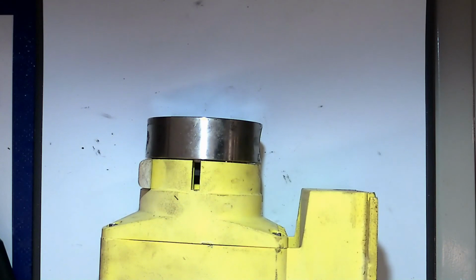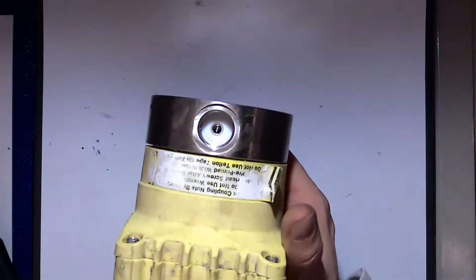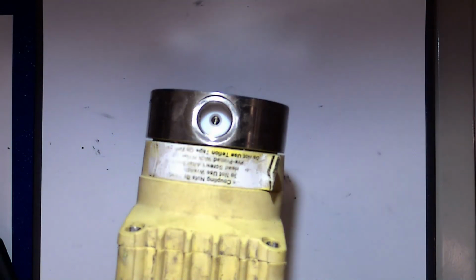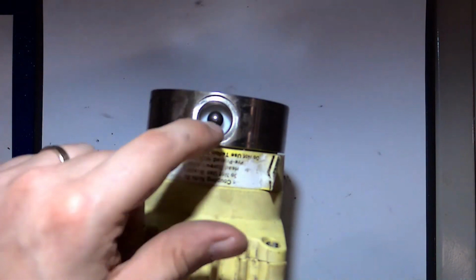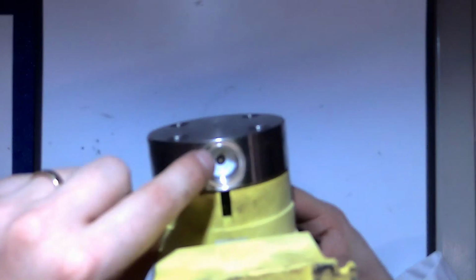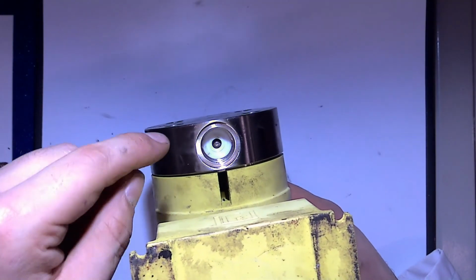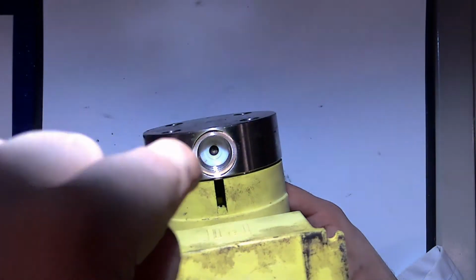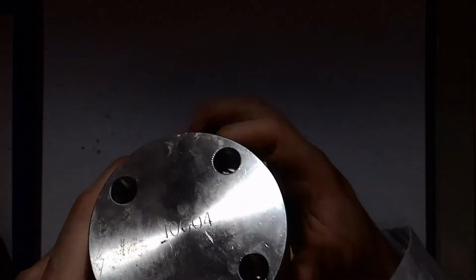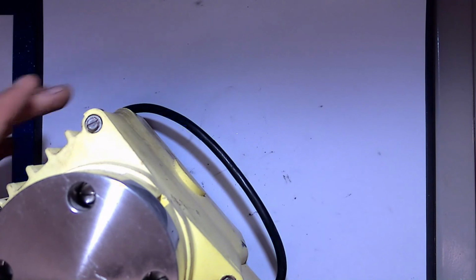Yes? Whereas on the top of the head part, you'll see a single hole, which means that the ball, put it back in, will seat, and therefore the fluid will not be able to pass back the way. Opposite is true on the other side. Your inlet, you can maybe see the ball inside there, means that the fluid can only flow this way. So as a whole, fluid flows from bottom to top. Okay, now I'll try and remove this head as well. Maybe sometime, so bear with me.